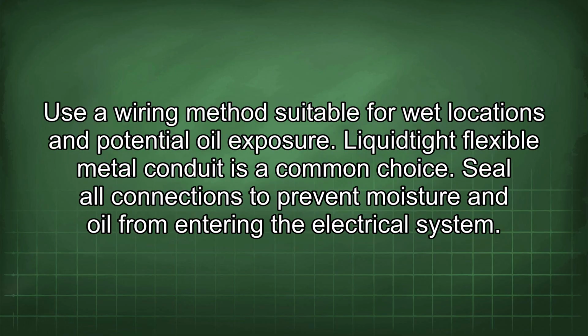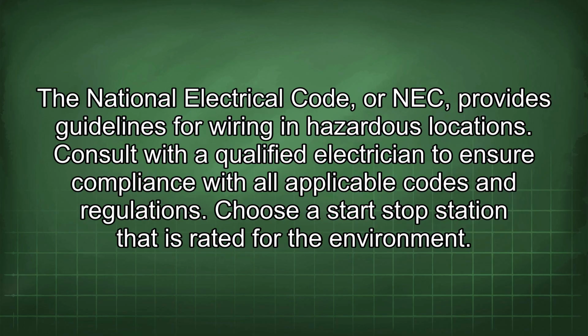Use a wiring method suitable for wet locations and potential oil exposure. Liquid-tight flexible metal conduit is a common choice. Seal all connections to prevent moisture and oil from entering the electrical system. The National Electrical Code, or NEC, provides guidelines for wiring in hazardous locations. Consult with a qualified electrician to ensure compliance with all applicable codes and regulations.